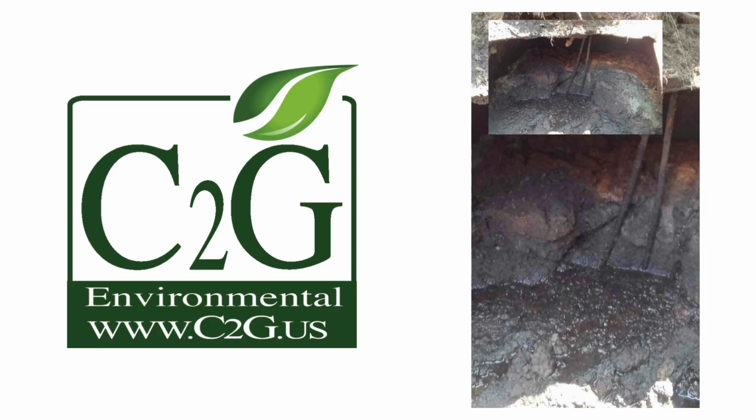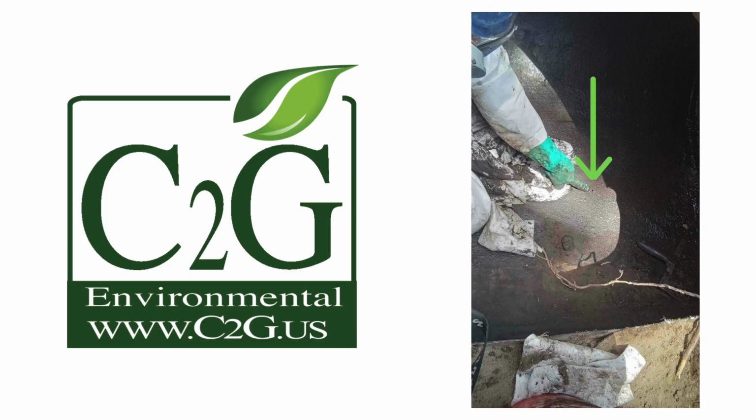In this case, we're looking at an underground tank that was filled with foam, but because the tank wasn't cleaned properly, the foam couldn't cure, resulting in a disaster for the customer. This customer purchased the home knowing it had an underground tank that had been previously abandoned and assumed the job was done correctly. The homeowner was shocked and confused when fuel oil started seeping into their crawl space, especially since the home uses natural gas.